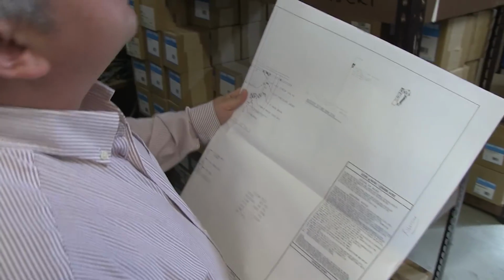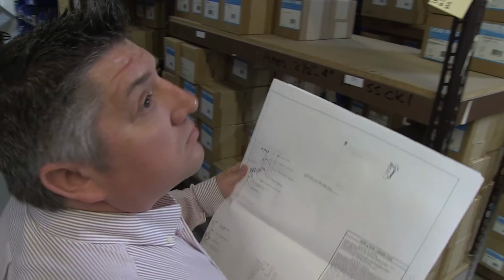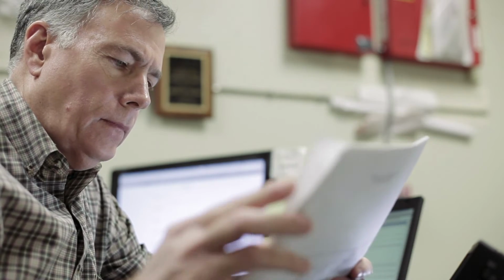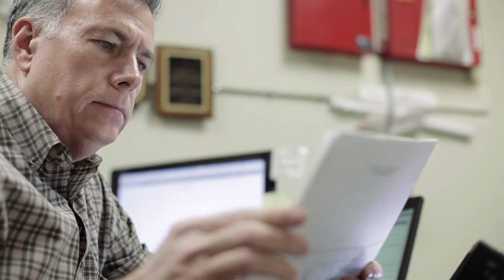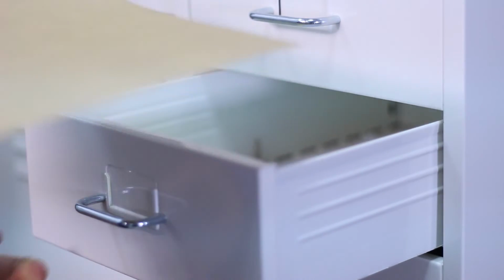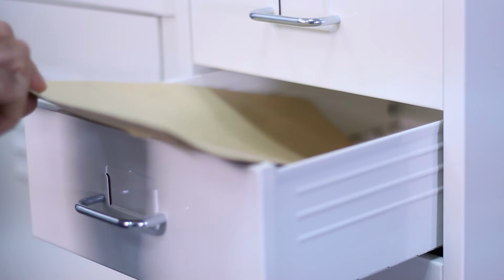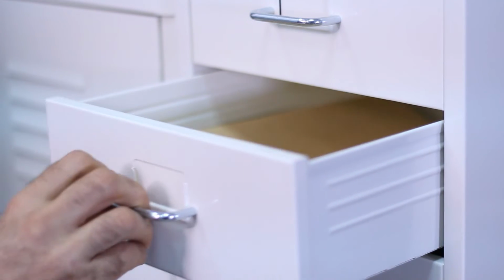Be sure to retain the as-built system installation drawings, hydraulic calculations, original acceptance test records, and device manufacturer's data sheets for the entire life of the system. Subsequent records must be retained for a period of 1 year after the next inspection, test, or maintenance of that type required by NFPA 25.